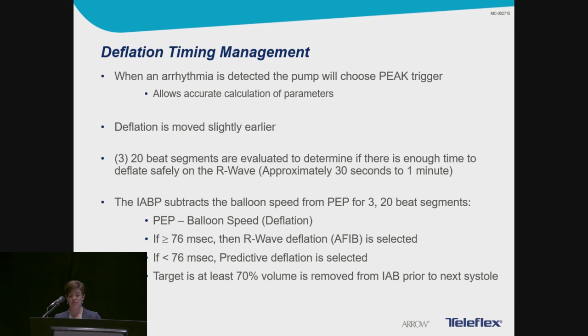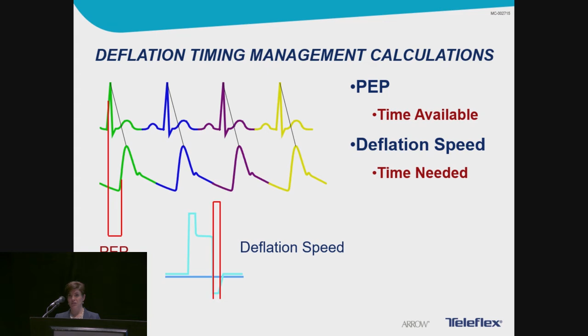Now, the pump assesses the measurement for a total of 60 beats, which depending on our heart rate can vary anywhere from 30 seconds up to a minute maybe. And if there's enough time to deflate the balloon at least 70%, the pump will select R wave deflation, or our AFib trigger. If not, it will remain in peak trigger, which allows deflation to occur earlier. This assessment is continuous when an arrhythmia is present, and the decision of the deflation timing method will update based on the current conditions. So again, it's a dynamic assessment continuing as long as the patient's in an arrhythmia. This slide just illustrates the two measurements of PEP and the balloon deflation time and essentially what is needed.